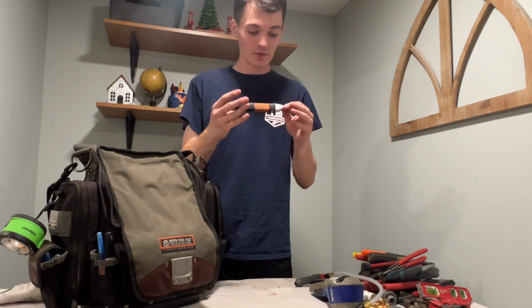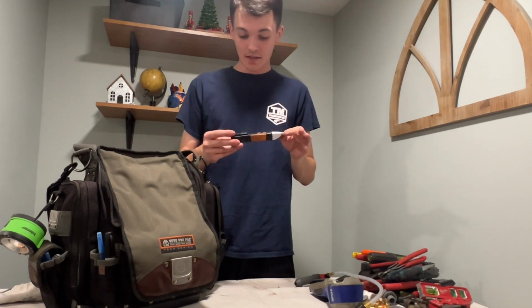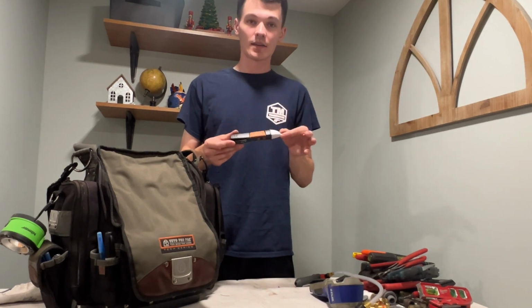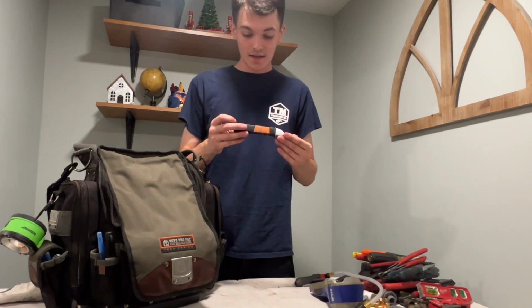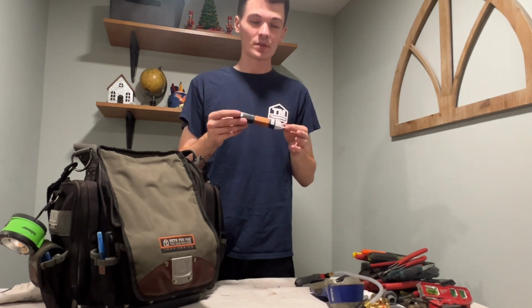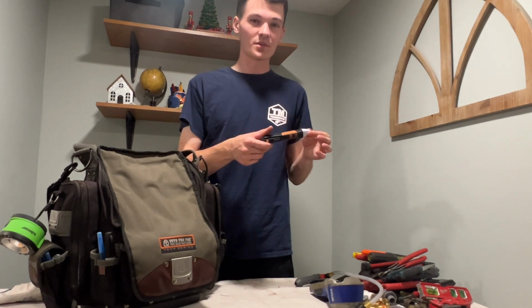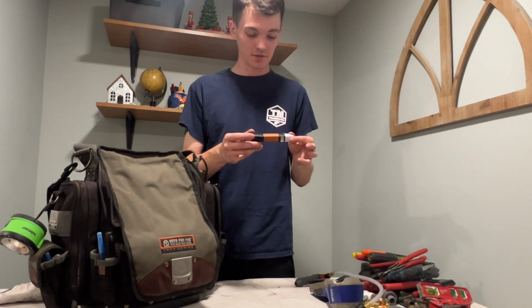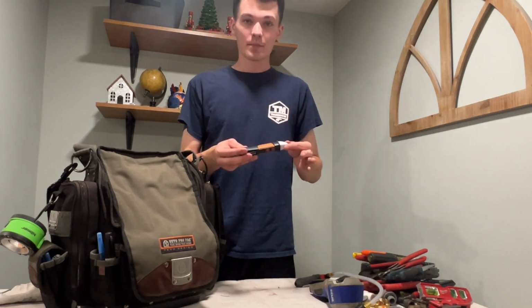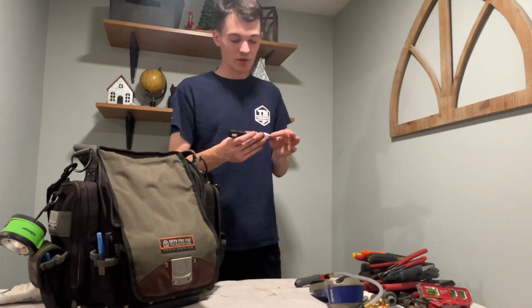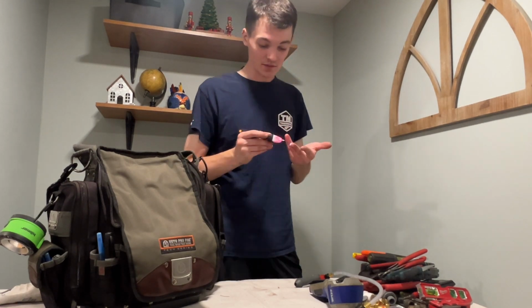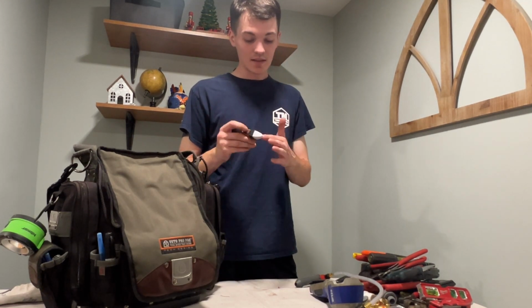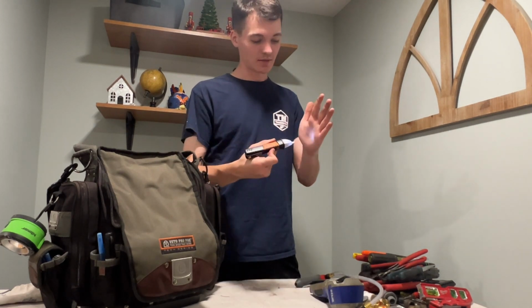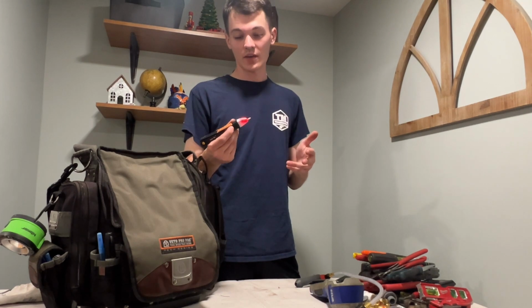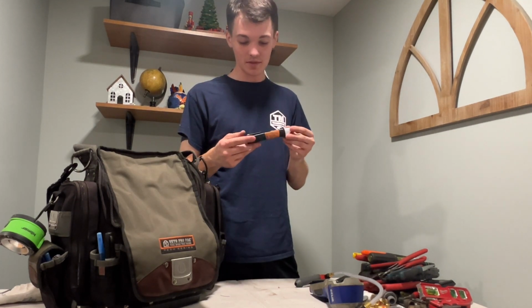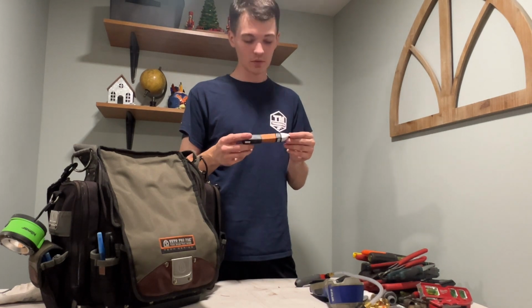Now this product I do have complaints on. It's made by Testo, a non-contact voltage tester that reads up to 1,000 volts, and as low as 50 volts AC. I've replaced the batteries a few times. It has an auto cutoff, but it takes a while to kick in. The flashlight on here is garbage, a gimmick, it hardly lights anything up. I've actually found this to be unreliable recently, so I'm going to switch to a Klein or a Fluke.